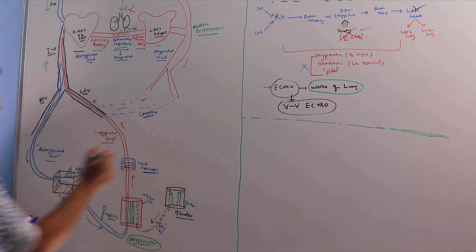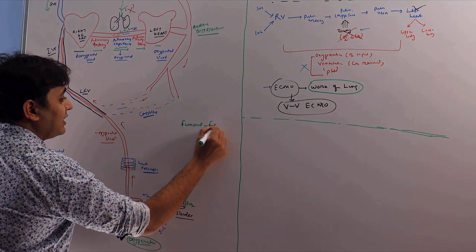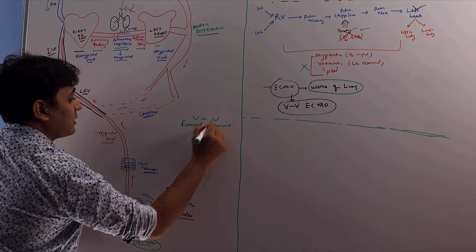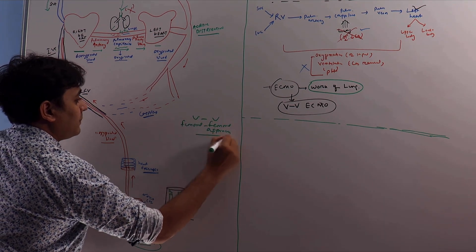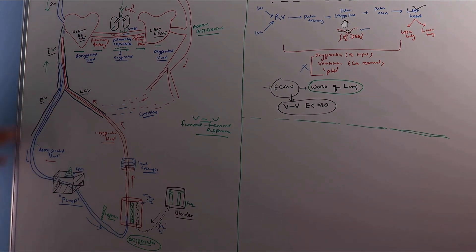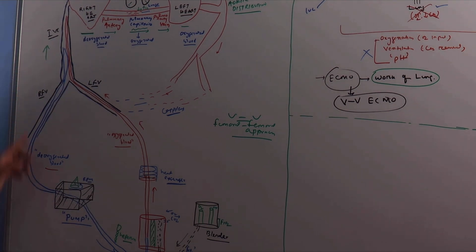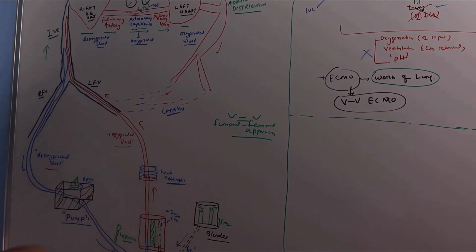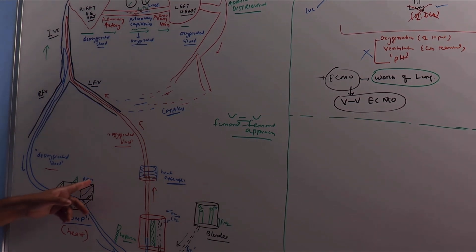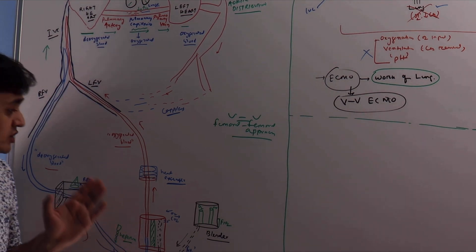Usually when you do a femoro-femoral approach — femoral is one vein, another femoral is another vein — this is a VV-ECMO femoro-femoral approach. We take the deoxygenated blood from the right femoral vein and use a pump to take the blood out. We have to create a negative pressure so the blood can be sucked out. In the ECMO machine the pump works as the heart — it has a motor running at a set RPM that creates the negative pressure.